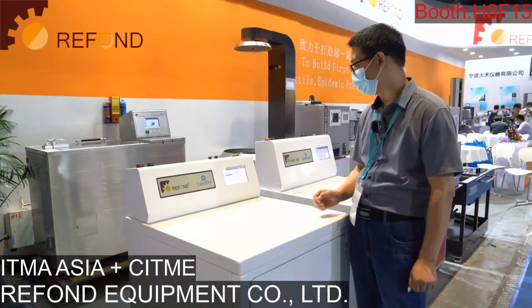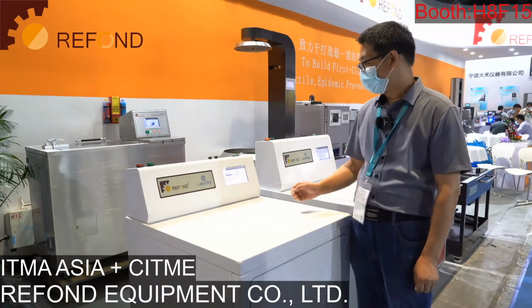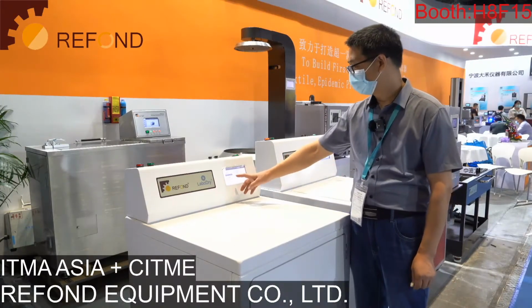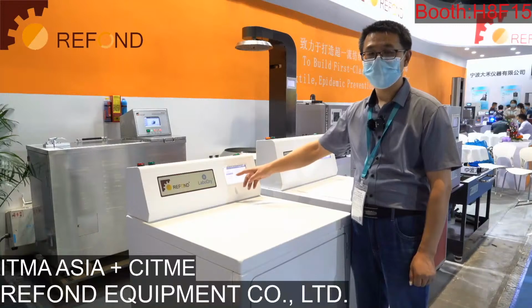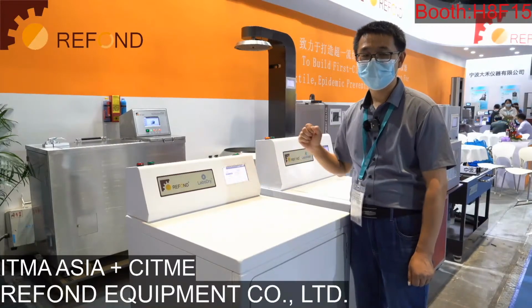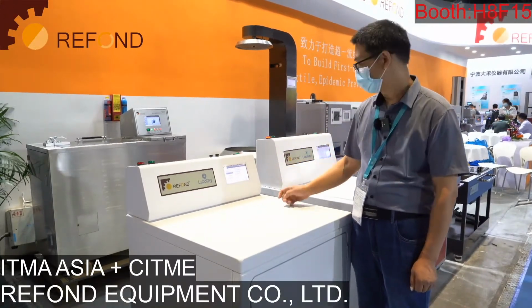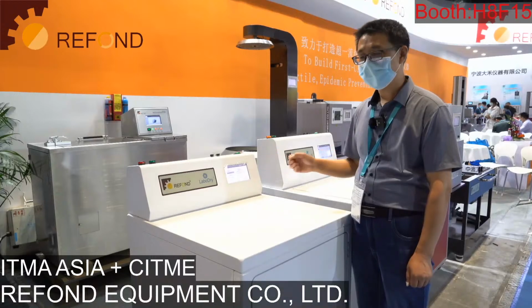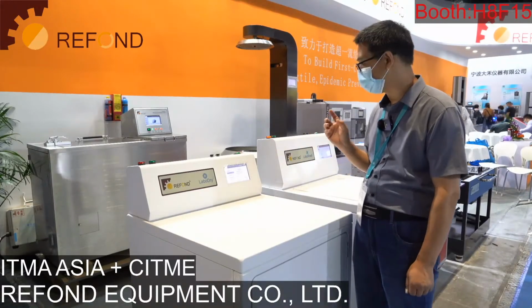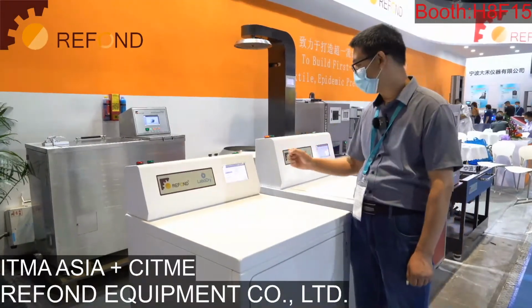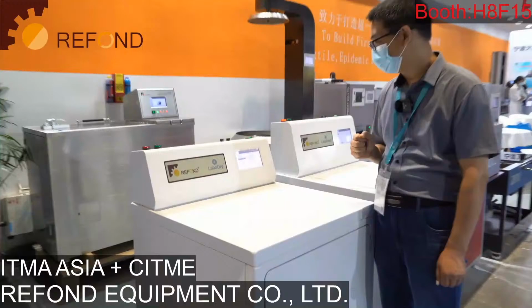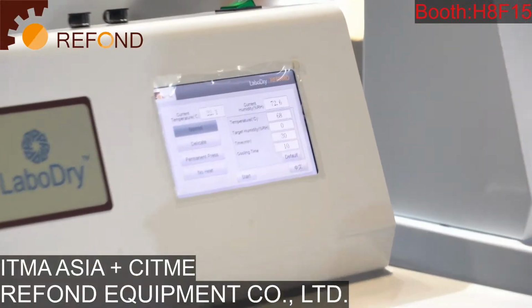AATCC testing standard. We have built in a standard testing program inside our touch screen. And in the touch screen, you can also set your own program. You can change the temperature, the testing time, cooling time.